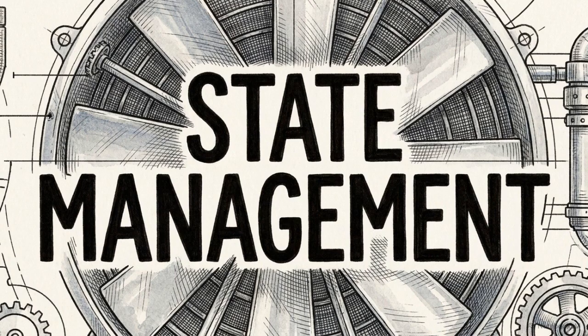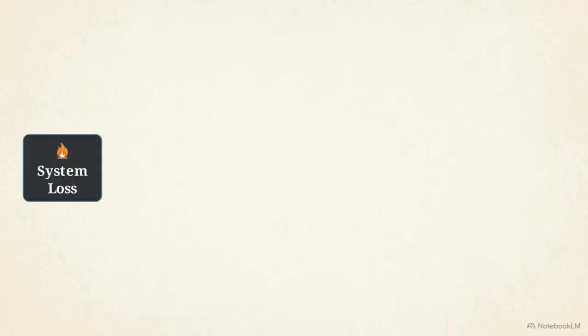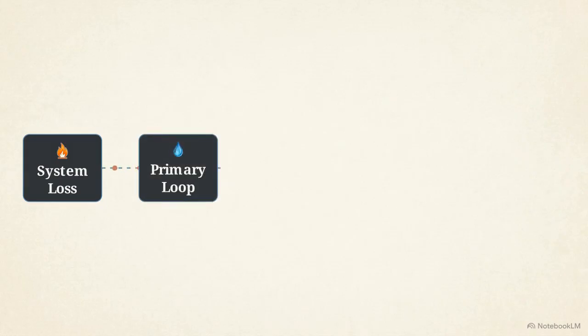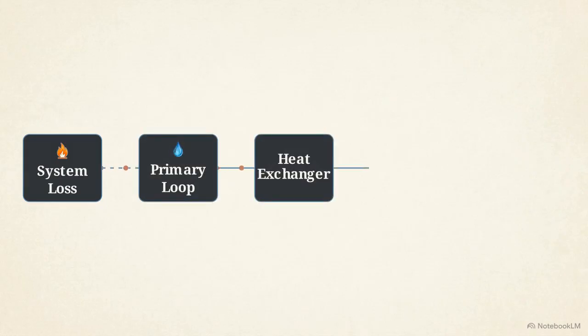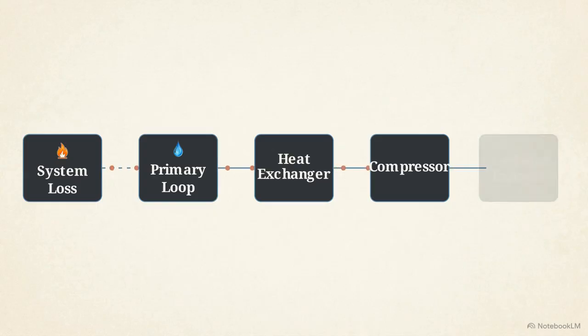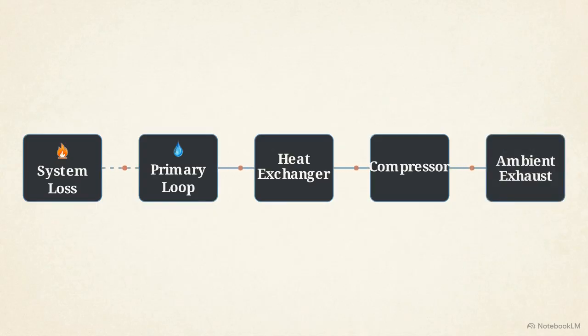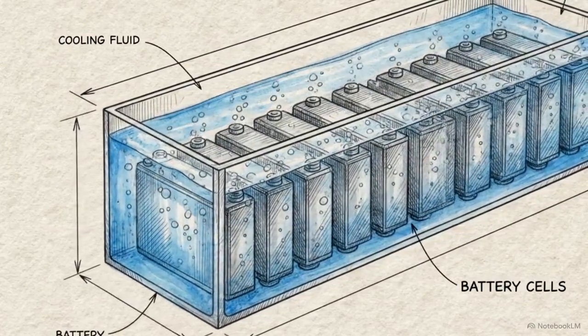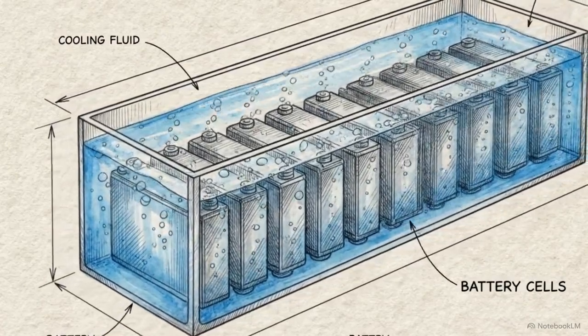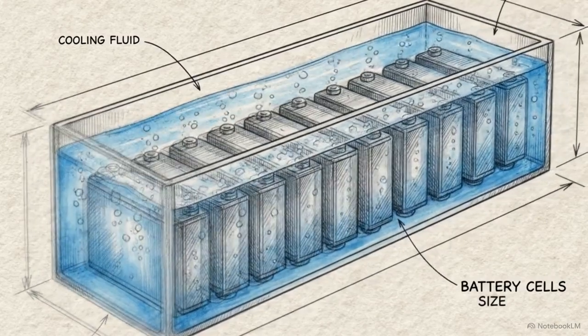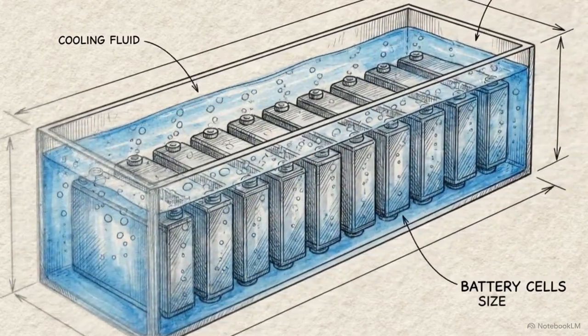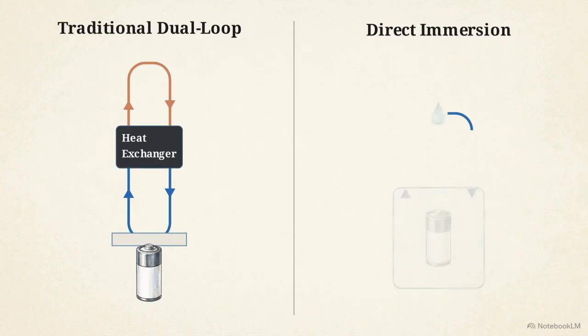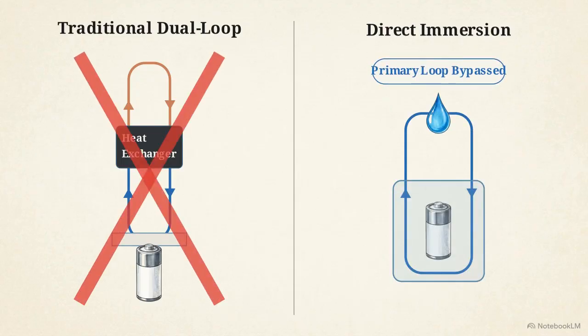The engineering achievement here is absolute control over energy state. The system successfully isolates the electrical inefficiency, converts it into a calculated thermal load, extracts it using optimized fluid dynamics, and rejects it into the atmosphere via mechanical refrigeration. Looking to the near horizon, the thermal management industry is actively prototyping direct refrigerant cooling and complete immersion cooling technologies. These systems aim to increase efficiency by bypassing the primary fluid loop entirely.